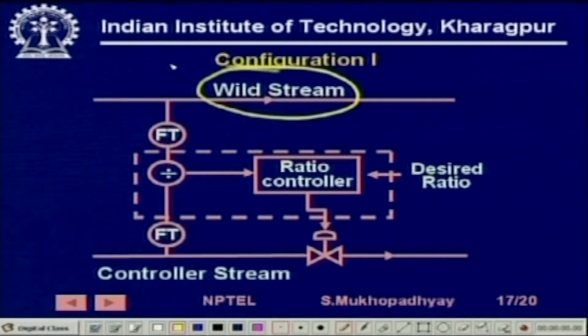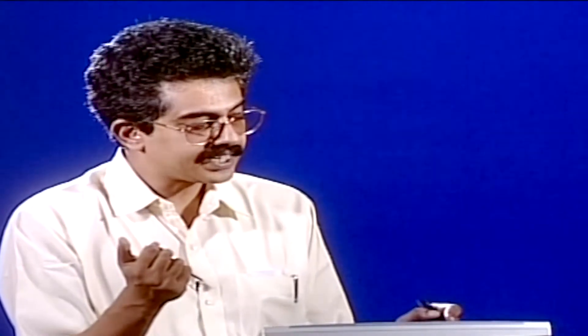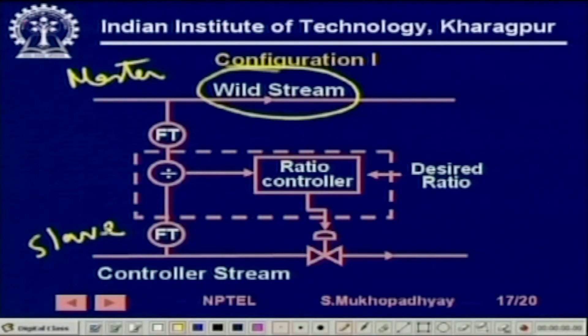We do not directly control the wild stream; it is controlled by other considerations. It is like a master stream which changes independently because of some operator change. And this is the slave stream or the controlled stream. Basically our idea is that if the wild stream changes we must change this stream such that the ratio of the volumetric flow rate in the wild stream and the volumetric flow rate in the controlled stream are maintained as constant. This is our objective.